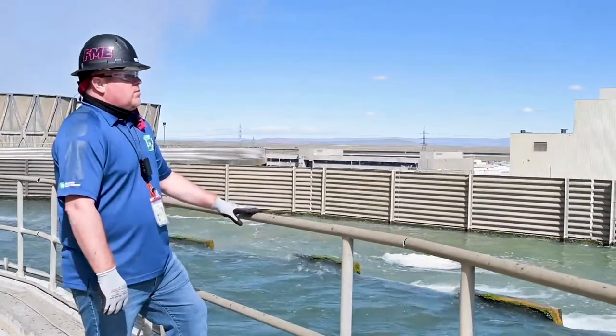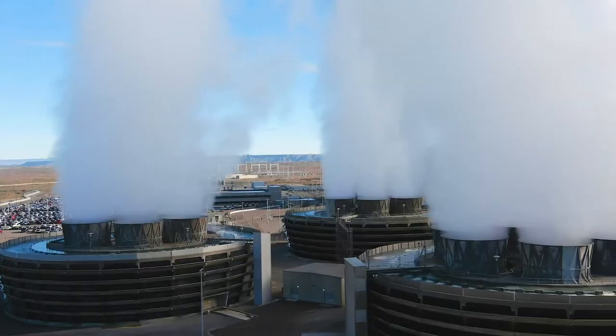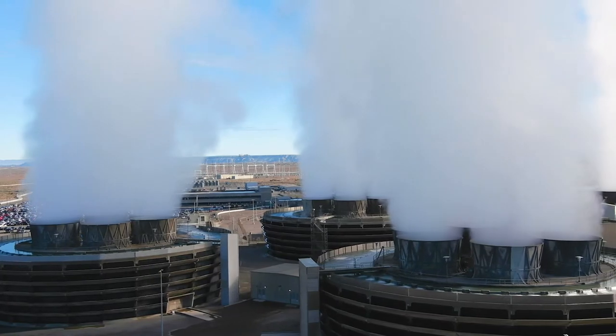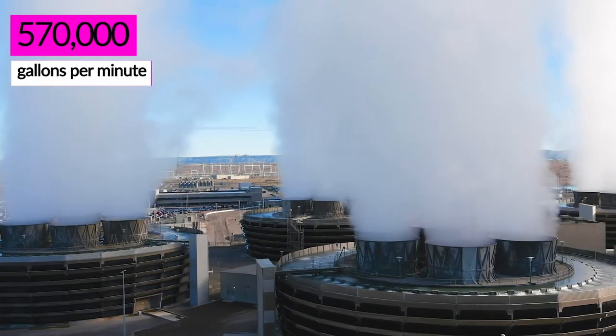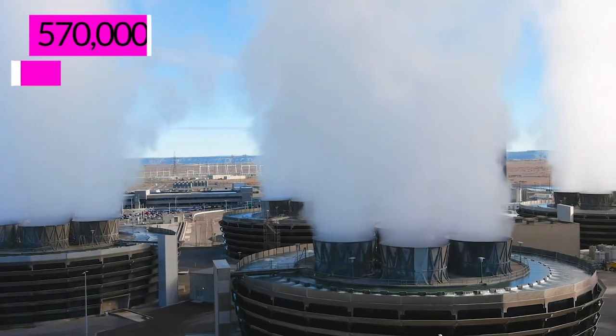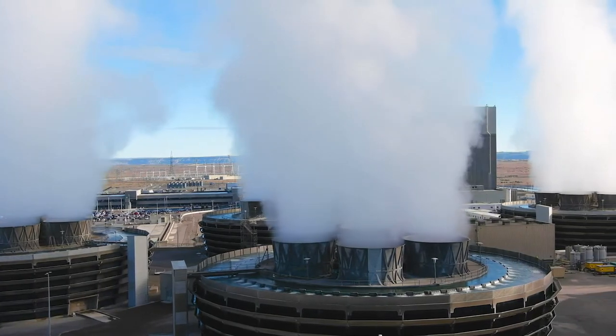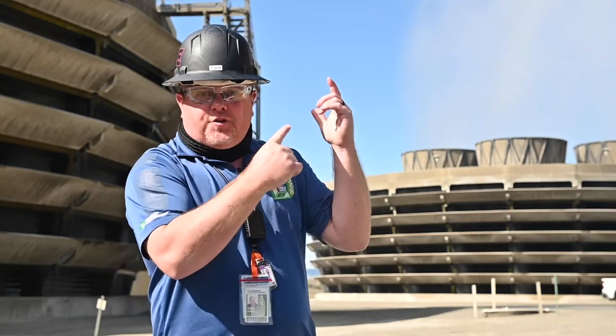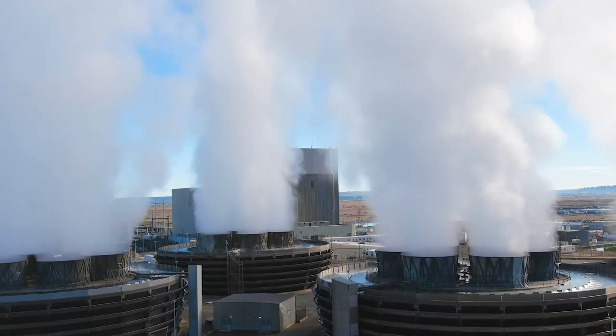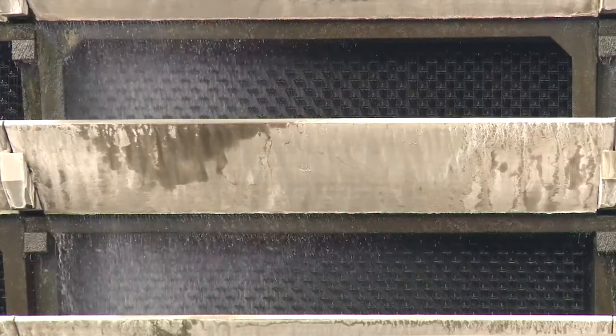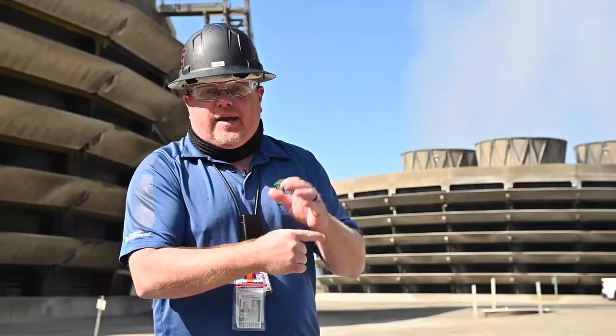Each of these cooling towers behind me are 65 feet tall and 200 feet at the base, with six fans on top. Water from the condenser is pumped into them at 570,000 gallons per minute into large canals at the top of each cooling tower, where fans blow air across the water, causing the heat to evaporate into the atmosphere. The large plumes going up into the air behind me are water vapor.